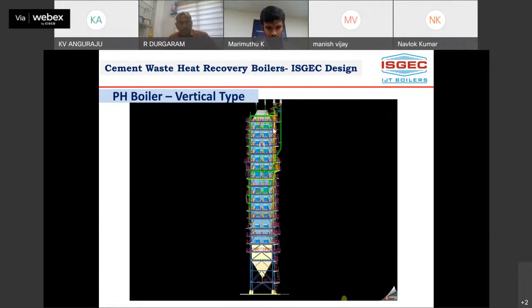This is a preheater boiler. It's a tall boiler with accessible platforms and everything provided all around. Then the hammering arrangement is always decided based on the width of the section. There is a bank, and the effectiveness is checked, whether one side or both sides, based on the width of the coils and length of the coil. Based on the length of the coils, whether it's single hammering or double hammering is decided. Then complete seal boxes and also safety protection covers, everything is provided in this boiler.